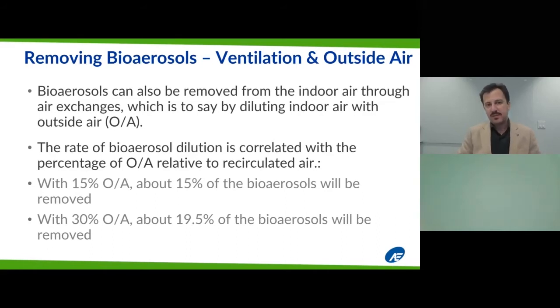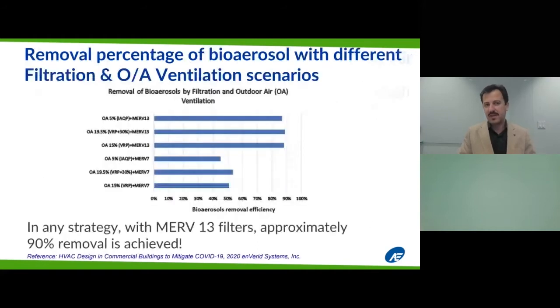We can remove these aerosols from indoor air through air exchanges, which is to say by diluting the indoor air with outside air. Now, the rate of bioaerosol dilution is correlated with the percentage of outside air relative to the recirculated air. As an example, with 15% outside air, you can remove about 15% of the bioaerosols, while by doubling that number up to 30%, the removal percentage is going to be only 19.5%. A very important note here is that these rates are based on the ASHRAE 62.1 ventilation rate procedure, which is based on liters per second per square meter and liters per second per person. So for the designers, that's an important notification.